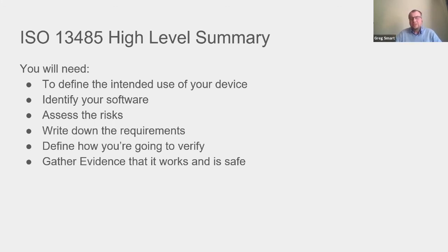So software identification is really important, product identification. The regulations, particularly the MDR, talk about something called UDI. So it's like a unique identification number for your product. And they talk about two different parts to that UDI. So there's what they call the device identifier and the production identifier.